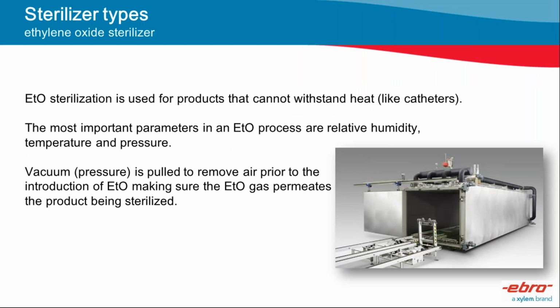Then we have the ethylene oxide sterilization. If you are familiar with gauze or band-aids or all those things that you need to cover your wounds, these need sterilization, but they cannot be treated using high temperatures. So the only way we can sterilize this kind of products is by ethylene oxide sterilization. And this kind of sterilization method must be validated regularly. And we have loggers that are explosion proof, EX certified. And these are the only loggers that you can use in this kind of sterilization machine.